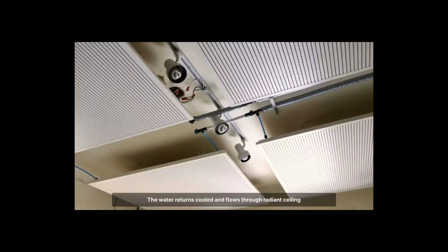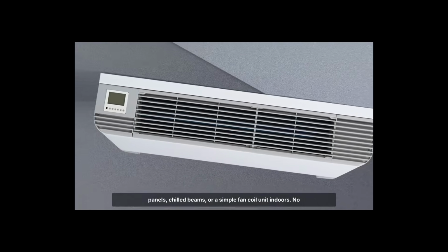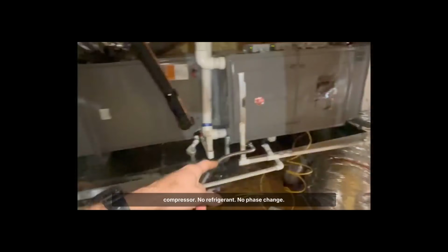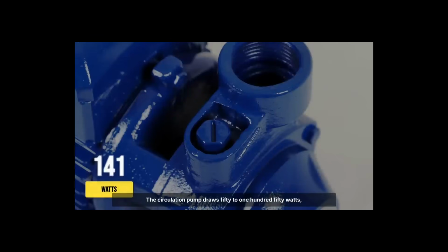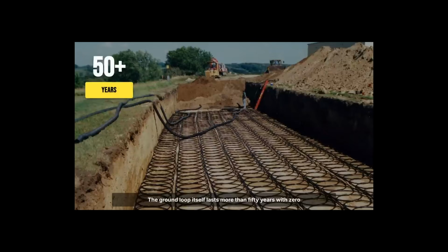The water returns cooled and flows through radiant ceiling panels, chilled beams, or a simple fan coil unit indoors. No compressor, no refrigerant, no phase change, just water carrying heat from your living room into the ground. The circulation pump draws 50 to 150 watts, less than a reading lamp. The ground loop itself lasts more than 50 years with zero maintenance.